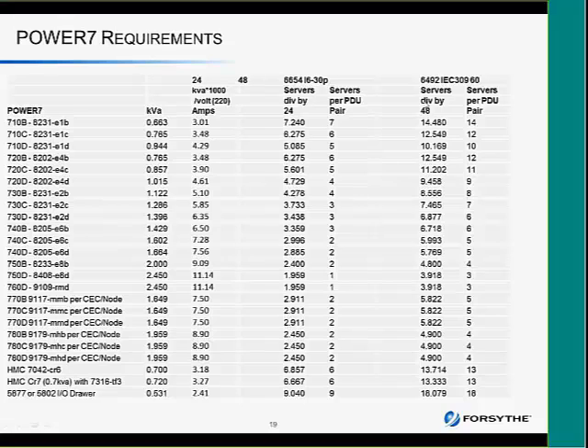This is just showing you that spreadsheet that I was using, and I just published it for 220 volts. So here you can see the different ratings for like an HMC, which is 0.7 kVA, 3.18 amps, and these are guesstimates based on calculation. So if I was on an L6-30P 30 amp, I could put 6 HMCs on it. I could put 7 710B models, but I can only put 2 780Ds on it. All right, and I've got the IO draw information here as well. So that's per PDU pair. So if I was to do a 780D, I could put 2 nodes across 2 PDUs.